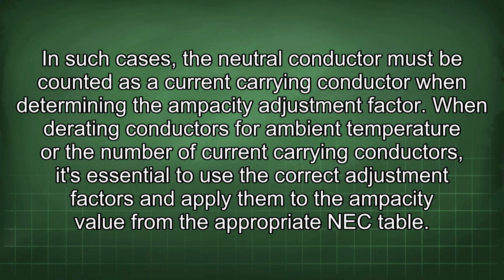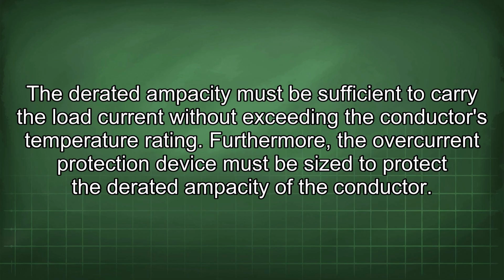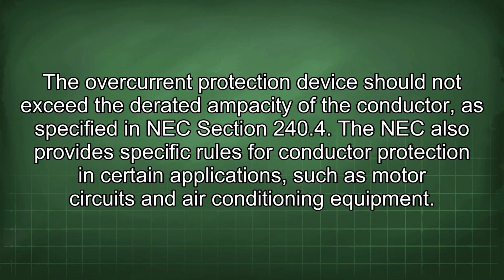When derating conductors for ambient temperature or the number of current-carrying conductors, it's essential to use the correct adjustment factors and apply them to the ampacity value from the appropriate NEC table. The derated ampacity must be sufficient to carry the load current without exceeding the conductor's temperature rating. Furthermore, the overcurrent protection device must be sized to protect the derated ampacity of the conductor. The overcurrent protection device should not exceed the derated ampacity of the conductor as specified in NEC section 240.4.